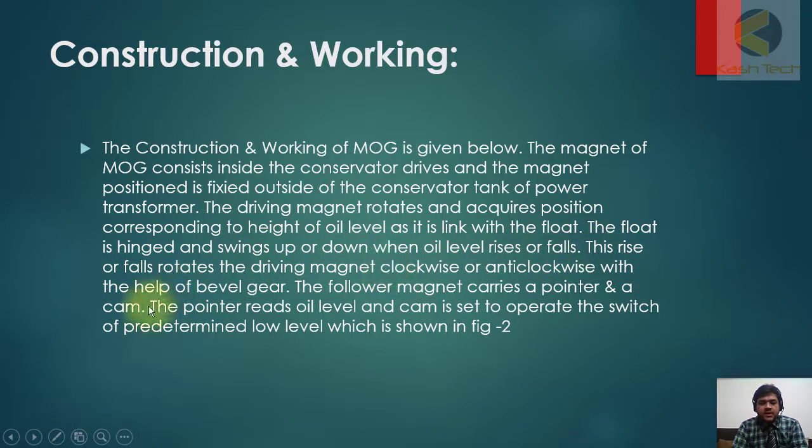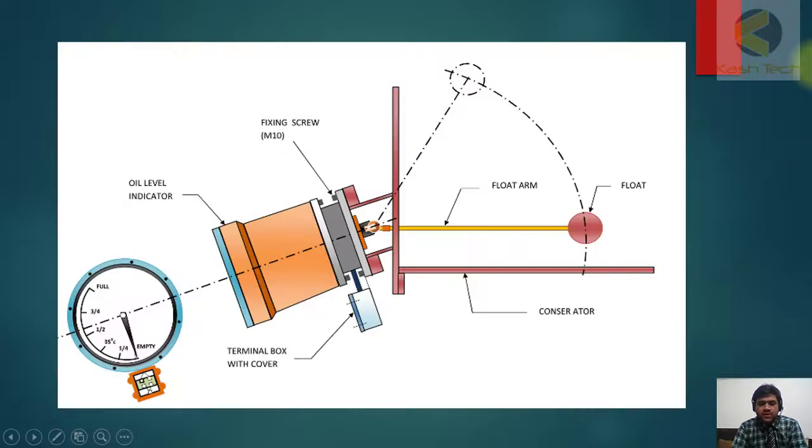This rise or fall rotates the driving magnet clockwise or anti-clockwise with the help of gear. The follower magnet carries a pointer and a cam. The pointer reads oil level and the cam is set to operate the switch at predetermined level which is shown in figure two. So again we'll come back.